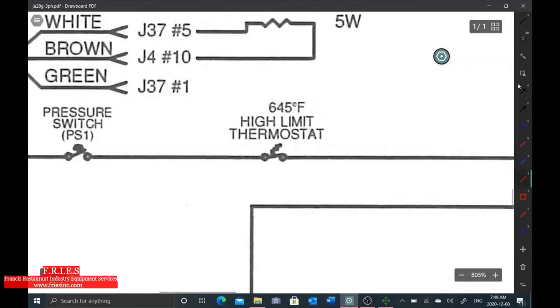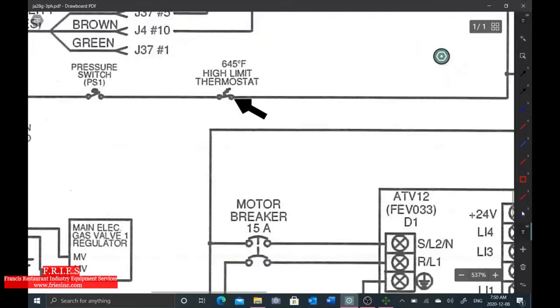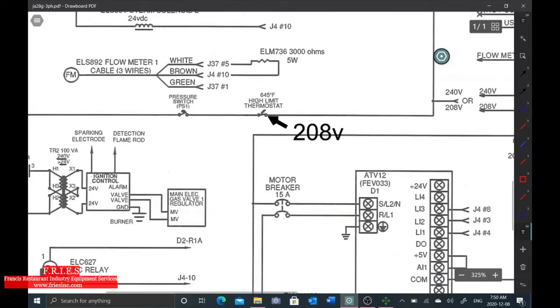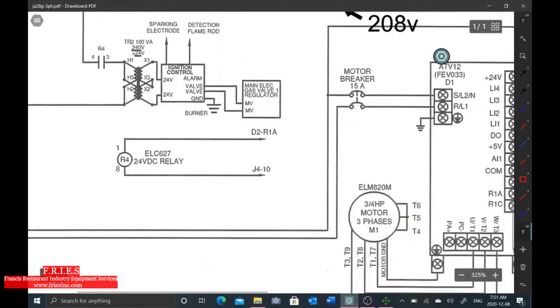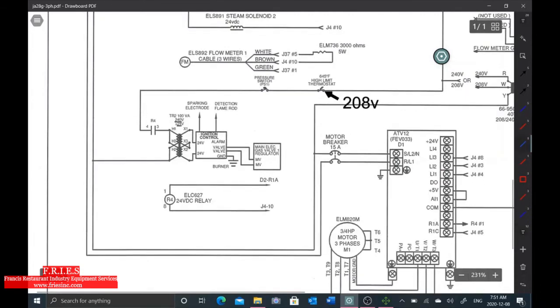So whenever testing across, first thing you have to do, confirm there's voltage coming in. I confirmed that. How we confirmed that, we went from there to L2. So when I tested to that point right there, I had 208. Okay, that test was done. From this test point here to my blue side of the circuit, which is my L2 right here. Okay, so I've tested from inlet to here. Now when I tested the outlet, I was getting 0 volts.